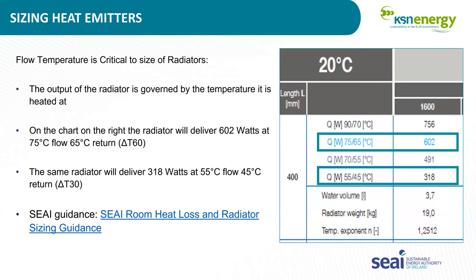Now, historically, radiators tended to be oversized, so there's a little bit of a buffer there. Another thing that we find is that in combination with the installation of a heat pump, insulation or heat loss reduction measures happen at the same time, so sometimes the load is reduced as well. There's the link there in blue at the bottom, if anyone wants to look for SEAI's guidance on heat loss and radiator sizing.